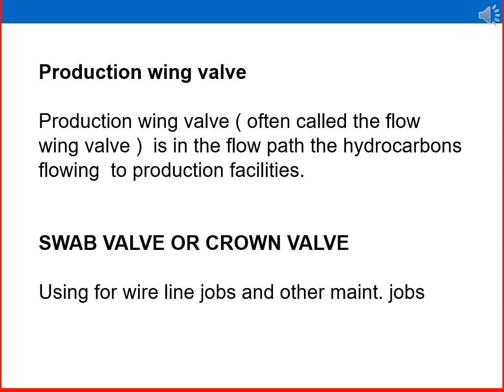Two other important valves in the Christmas tree are the production wing valve and the swab valve. The production wing valve — often called the flow wing valve — is in the flow path for hydrocarbons flowing to the facilities. It is the main valve to divert flow from a well to a production facility. The swab valve, or crown valve, is used for wireline jobs — that is, maintenance jobs in the subsurface reservoir or flowing tubing. In normal production, the swab valve is closed and the production wing valve is open.